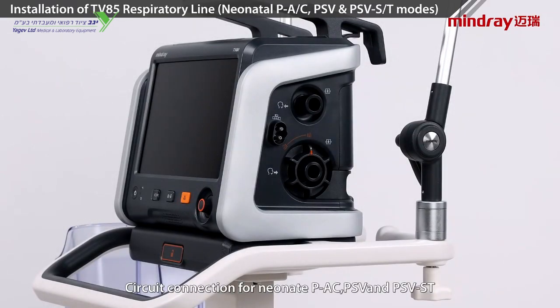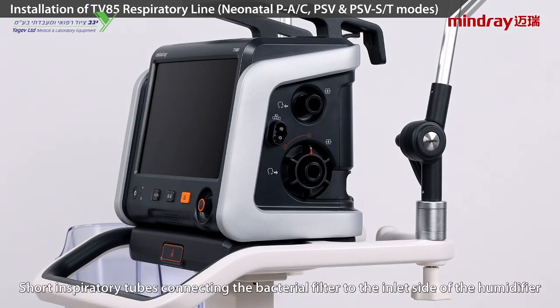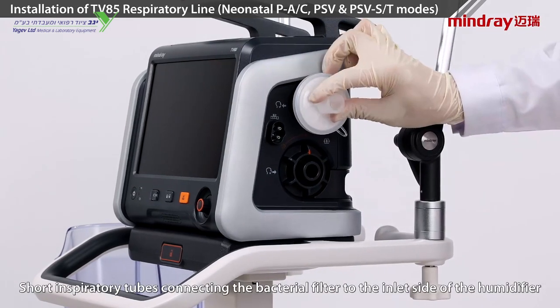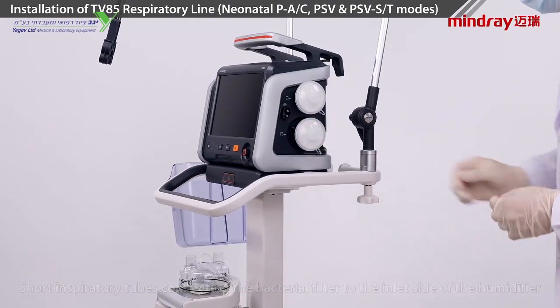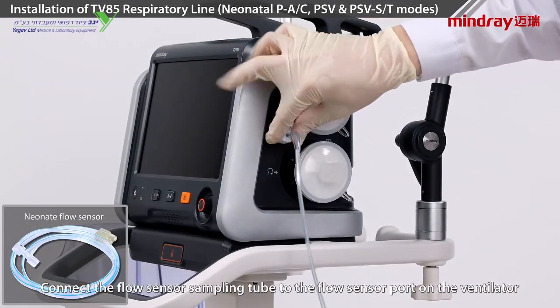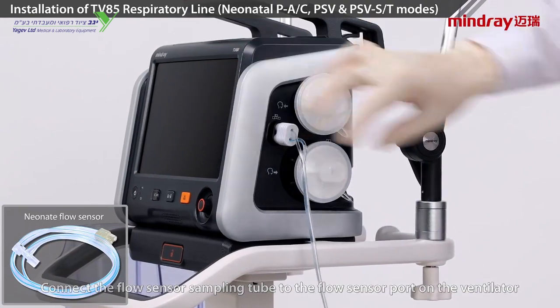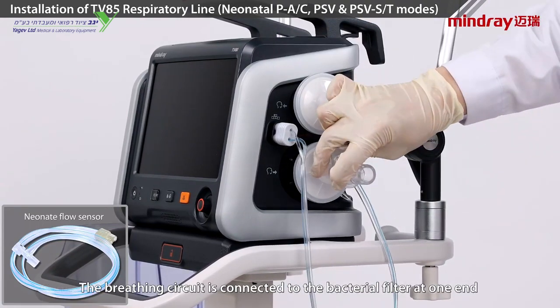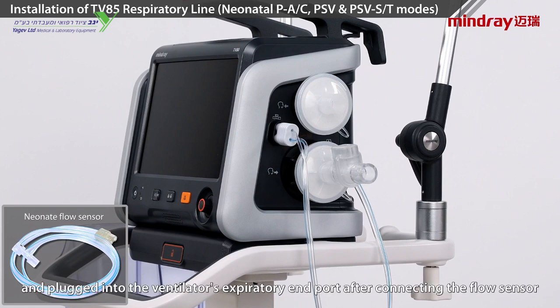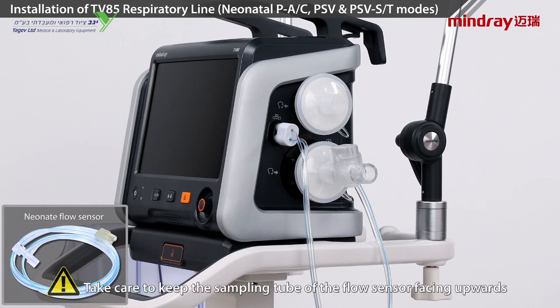Circuit connection for neonate, pressure assist control, pressure support ventilation, and pressure support ventilation spontaneous timed. Connect the short inspiratory tube to the bacterial filter and the inlet side of the humidifier. Connect the flow sensor sampling tube to the flow sensor port on the ventilator. The breathing circuit is connected to the bacterial filter at one end and plugged into the ventilator's expiratory end port after connecting the flow sensor. Take care to keep the sampling tube of the flow sensor facing upwards.